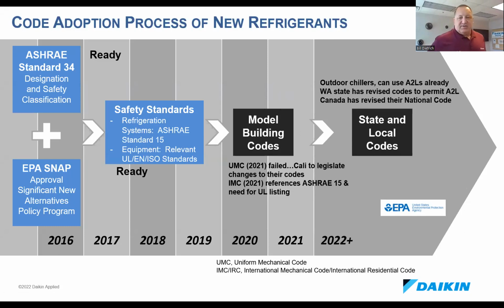Because chillers are considered indirect systems. If that chiller leaks refrigerant when it's outdoors, it either goes outside or it goes into the water loop. If the chiller's indoor in a mechanical equipment room, that equipment room is not considered the occupied space. So it's considered an indirect system, so a bit lower risk.